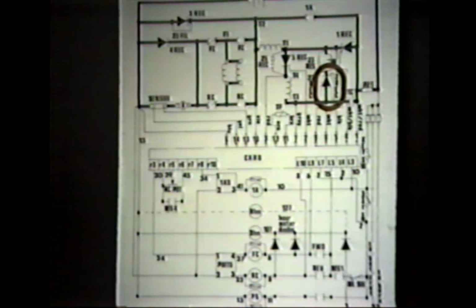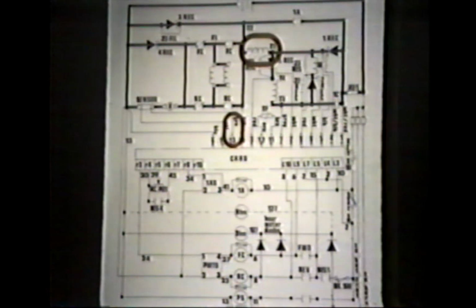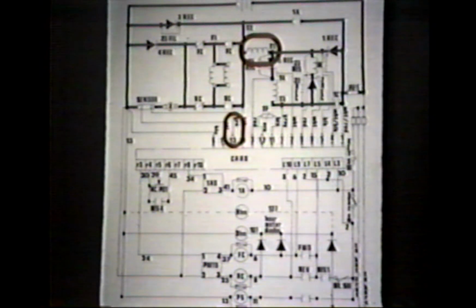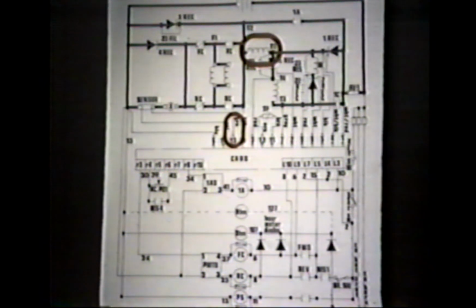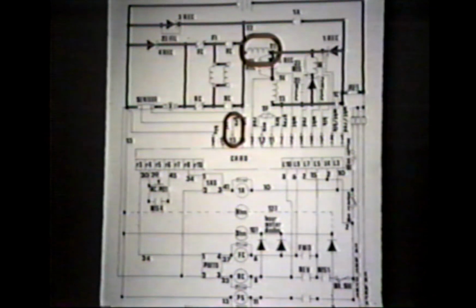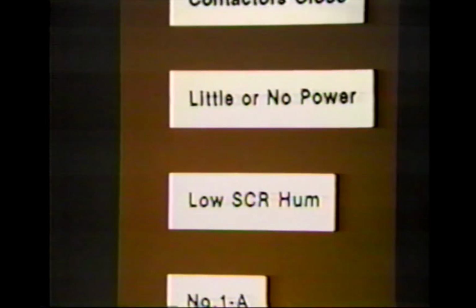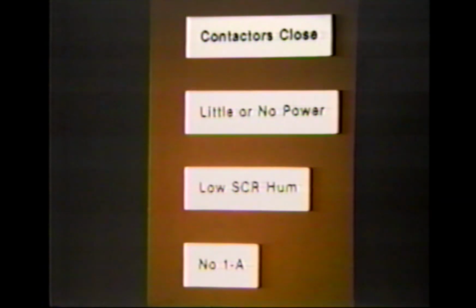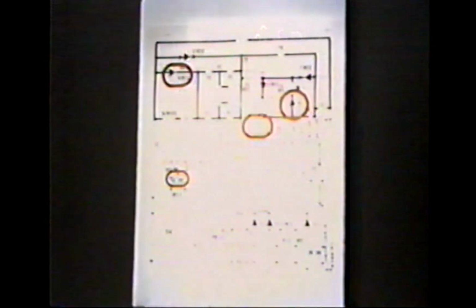Also, check the 2 rec for an open condition or no gate signal from the card. Check the green wire from the sensor to the card plug and the transformer primary T1 to T2 for an open. If all of the above items check good, replace the card. The next symptom is contactors close, little or no power, low SCR hum, and no 1A. Check the following items circled in red on the wiring diagram. The accelerator pot adjustment and operation, the 4 rec for a shorted condition, an open or heated thermoprotector, and a shorted 2 rec.